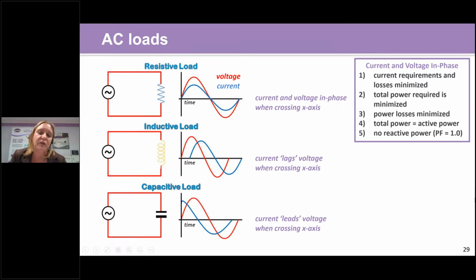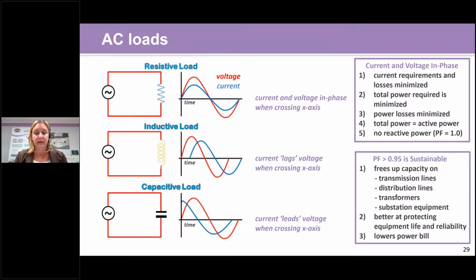So if you can have a resistive load, or correct your inductive load so it behaves like a resistive load in your plant, your current requirements and losses are minimized. Your total power required is minimized. That directly hits your electricity bill. Your power losses are minimized. Your total power is your active power, and there's no reactive power. So being greater than a power factor of 0.95 is sustainable. It frees up capacity on transmission lines, distribution lines, transformers, substation equipment, and it's better at protecting your equipment, life and reliability, and it lowers your bill.